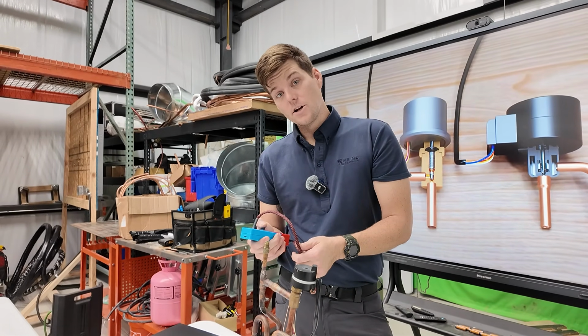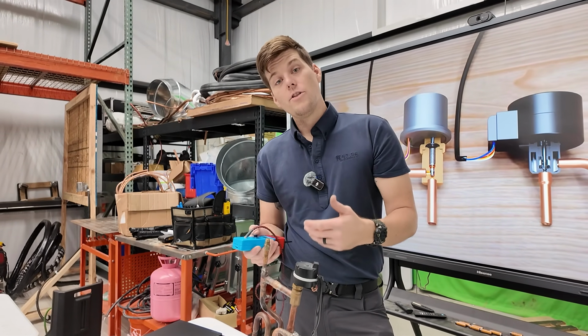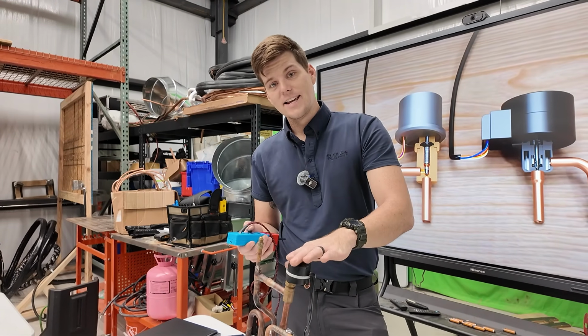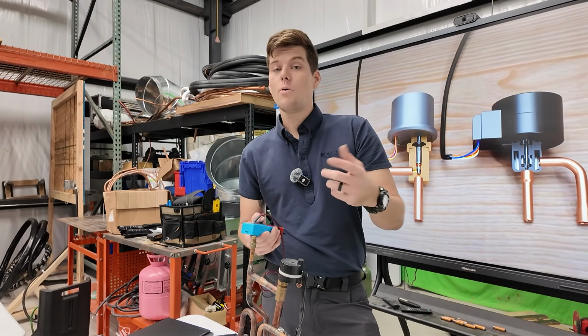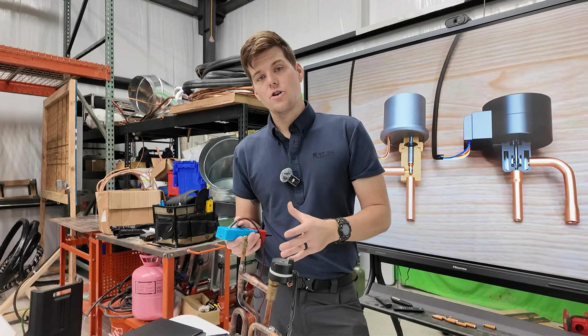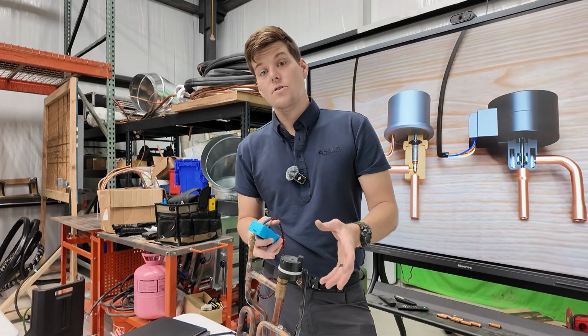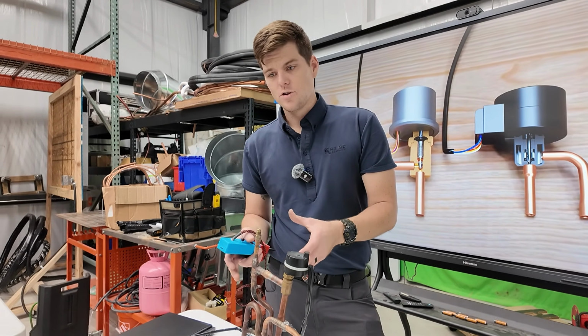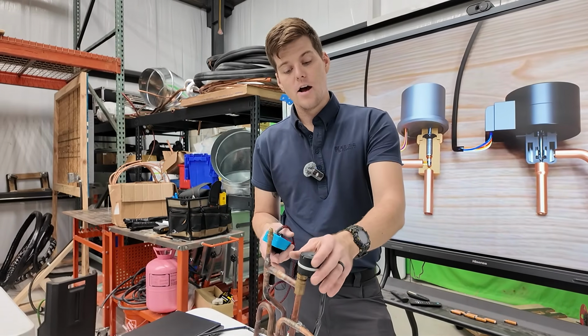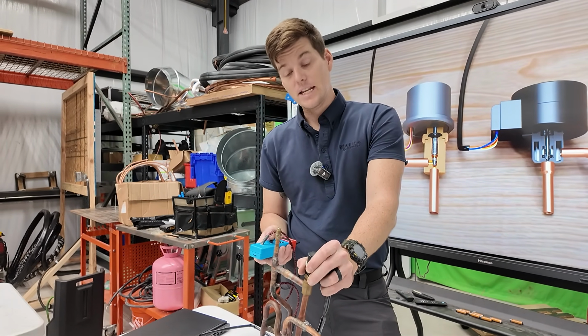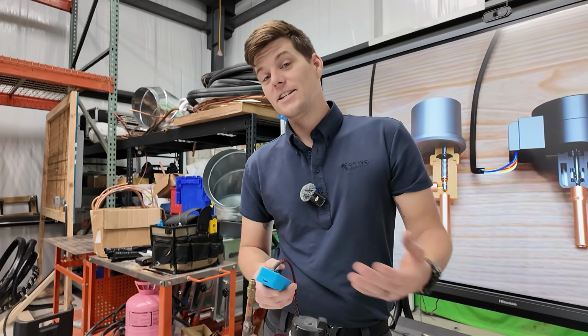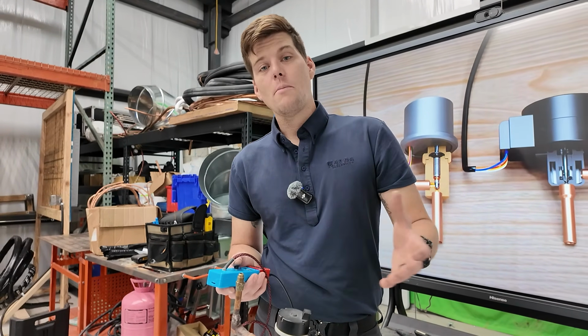For this one, I'll go ahead and initiate turbo mode, a mode you would use to drive the EEV 10 times faster than a normal PCB. The important thing is that when you run it in turbo mode, it's designed to cause a valve that might be stuck and needs a little more torque to open up or close down fully if it's bleeding by. So we drive it in turbo mode, which is 10 times the speed of a normal PCB driver.